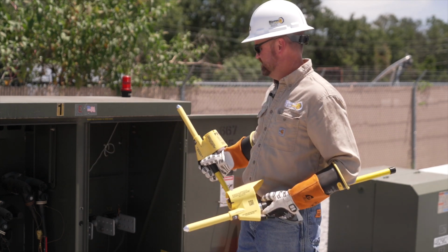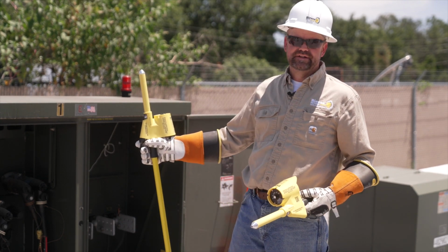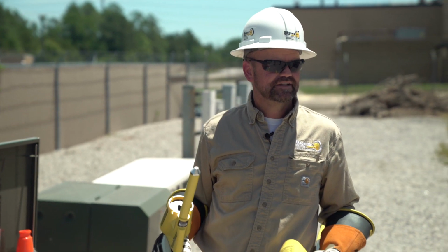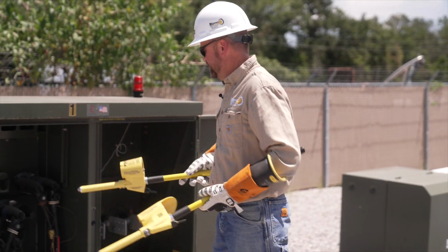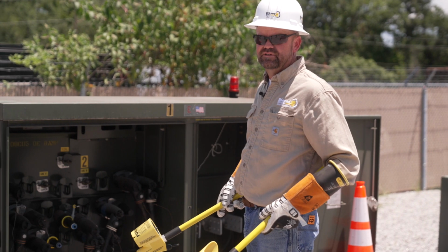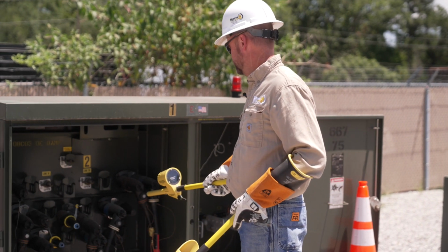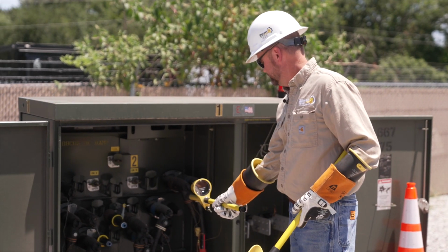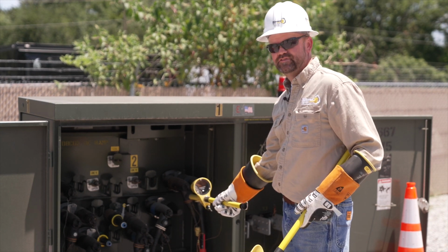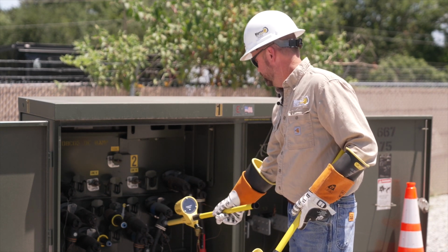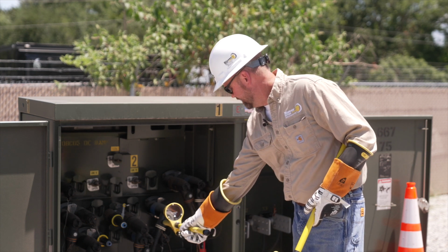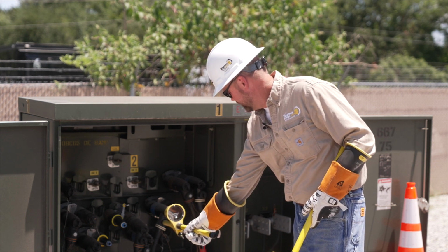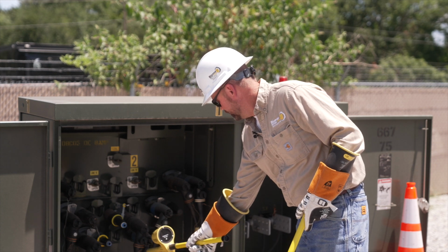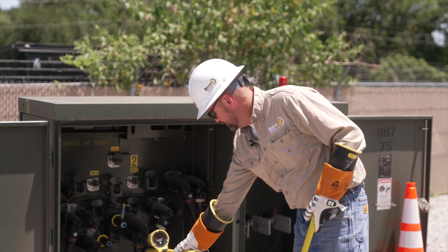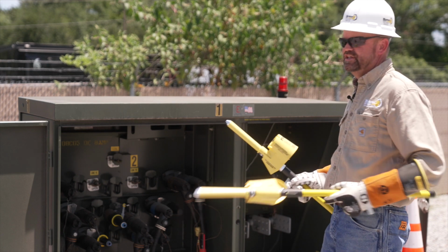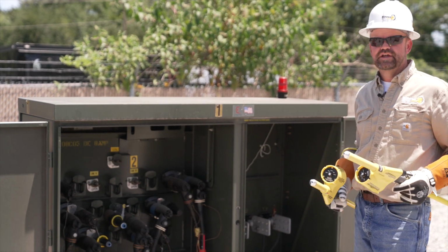So again, I just did my secondaries. I can do it on my primary. The first thing I'll demonstrate is on my capacitive test points. So again, I'll pick any two of the three with my reference probe. I get a white light. I know that capacitive test point is hot. Go to my second bushing. I get a white light. I know that capacitive test point is hot. And on my third, I also get a white light. So I'll know all three of these primary elbows are energized.